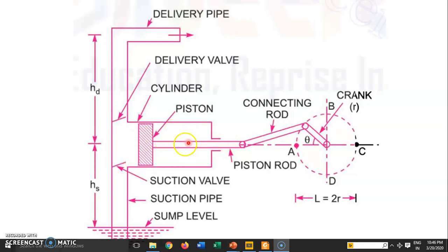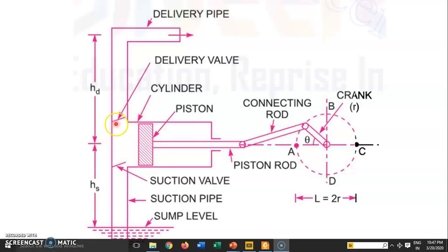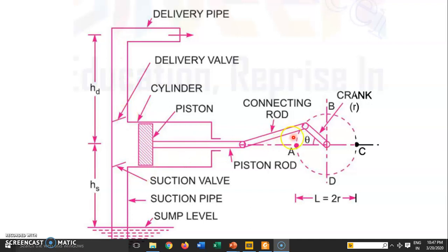Now the piston moves from right to left (delivery stroke). Whatever is inside the cylinder tries to go outside. The fluid pushes the suction valve, which closes and remains closed. It then pushes the delivery valve open, and the fluid between the piston and cylinder passes through the delivery pipe. So, during suction the fluid is drawn in, and during the delivery stroke whatever is there is pushed out through the delivery pipe — that is the working of the reciprocating pump.